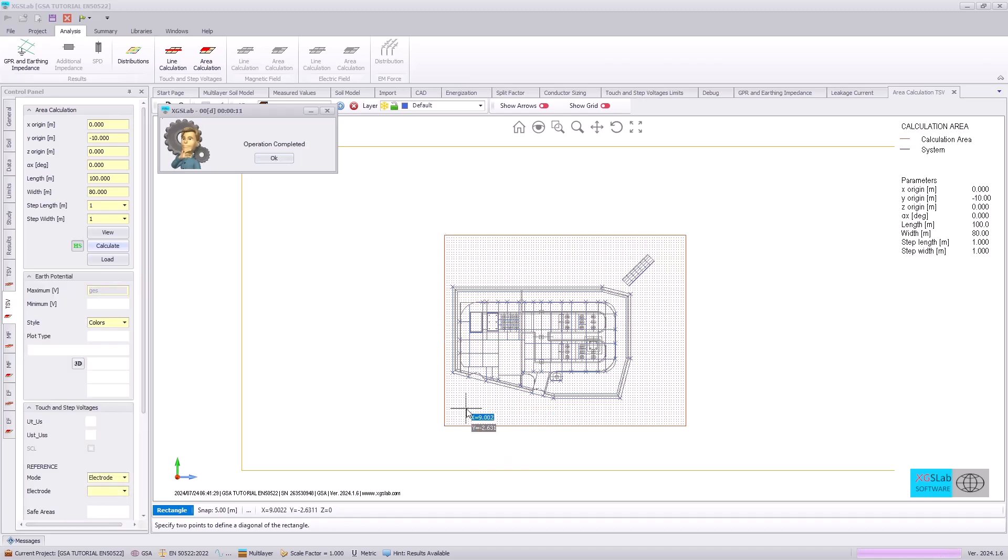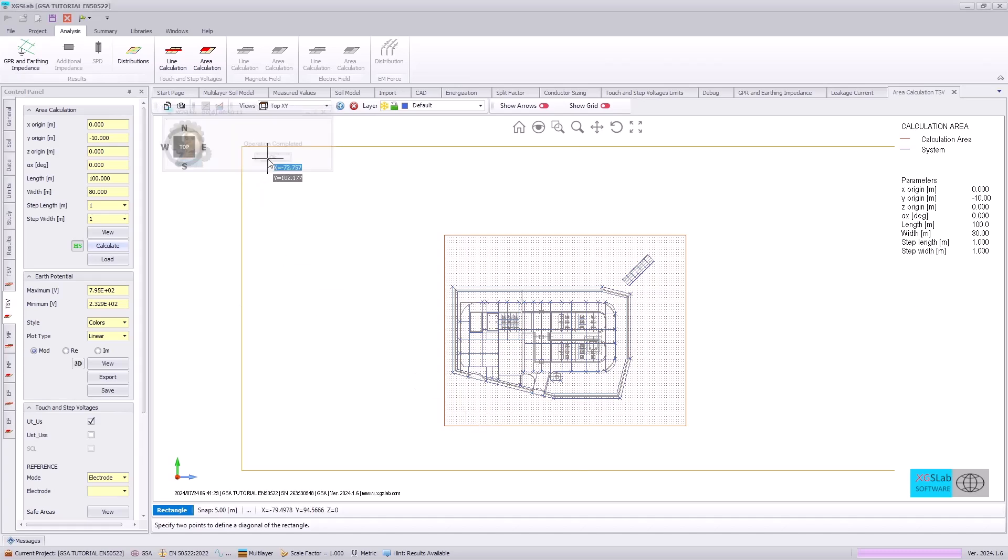This means that XGS lab will calculate the earth surface potentials at every point as specified in our area calculation. This is what's used to calculate the touch and step voltage, touch and step voltages, as well as the GPR earth potential rise.